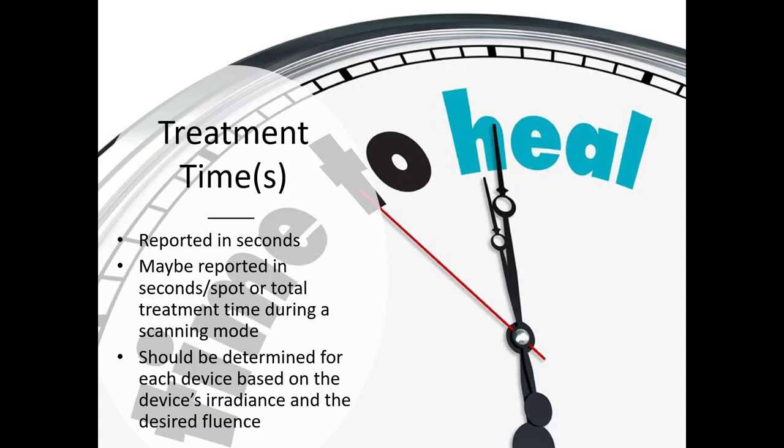Treatment time is typically reported in seconds. This may be reported in seconds per spot or total treatment time during a scanning mode. We'll discuss what a scanning mode is in just a minute. This should be determined for each device based upon the device's irradiance and the desired fluence for the treatment protocol.